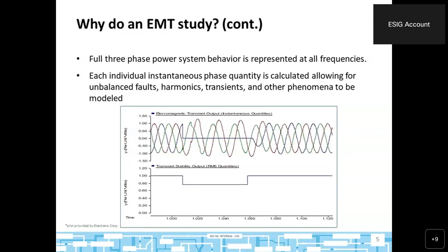ISO New England requires EMT studies to be done as part of the system impact study for every new inverter-based generating facility or elective transmission upgrade that utilizes power electronics as part of the facility or a network upgrade. Think of things like VSC, HVDC, and where they're adding a lot of STATCOMs in order to add a lot of reactive support. So I've listed here some of the different reasons to do an EMT study.